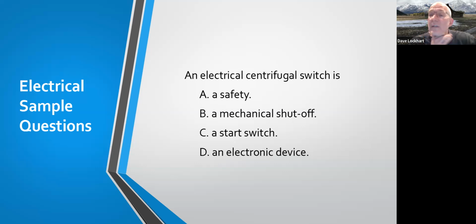So usually those are for like a high speed on a motor or some other spinning device, that if it goes faster than it's expected, or maybe in some cases, well, this says mechanical shutoff switch, but I've also seen centrifugal switches that do close. Once it gets to a speed, it'll close and let you know that something can operate. But the correct answer on this is a mechanical shutoff switch. And I guess saying shutoff, even if it was slowing down, it would then open up, but it's a mechanical shutoff switch. Basically, mechanical spinning is what is going to activate that switch, change state at that point.